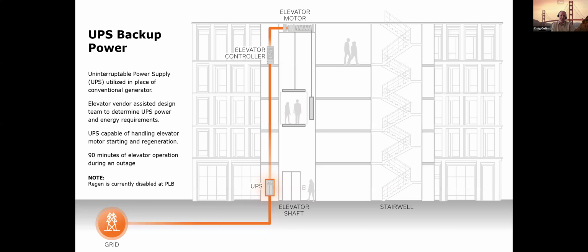So if we have a momentary interruption in the grid power, or if we're testing our microgrid system, which we do pretty regularly, the users of the elevator would not notice the switching events associated with our microgrid and would not notice a grid outage. The UPS is able to provide 90 minutes of backup operation. It took some doing to calculate that energy quantity. We worked closely with the elevator vendor to determine the power demand and also the energy consumption of the elevator, basically running up and down fully for a full 90-minute duration, and that's how we sized our UPS so that we would meet code.